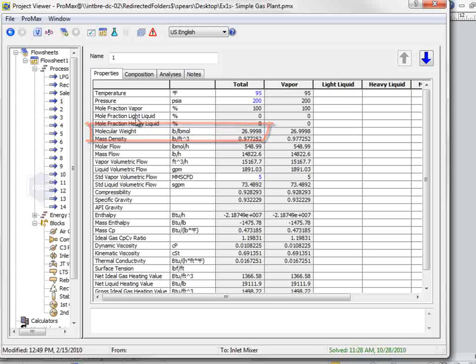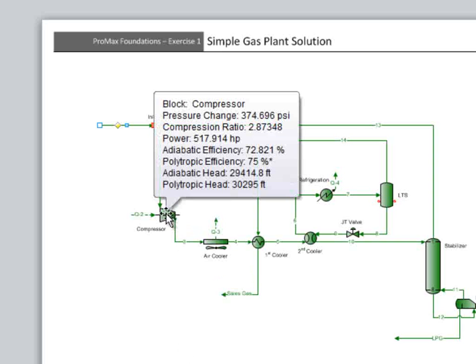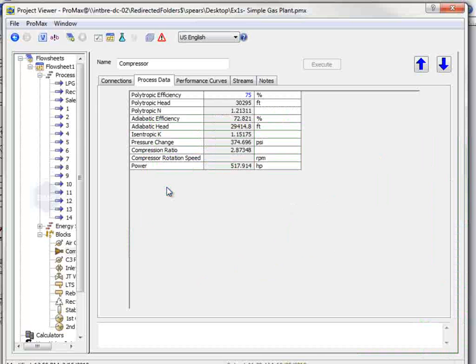The second question asks about the compressor brake power, discharge temperature, and head. The brake power and head are both properties of the compressor, so we can double click on the compressor and look on its process data tab. The brake power is 517.9 horsepower.